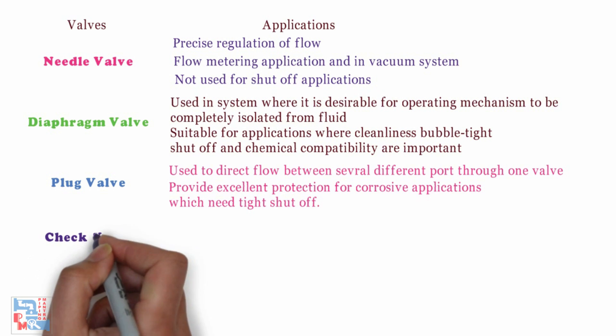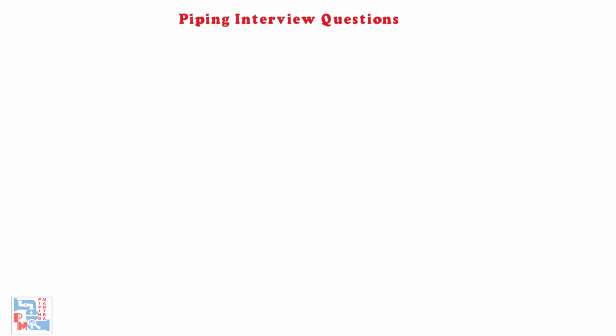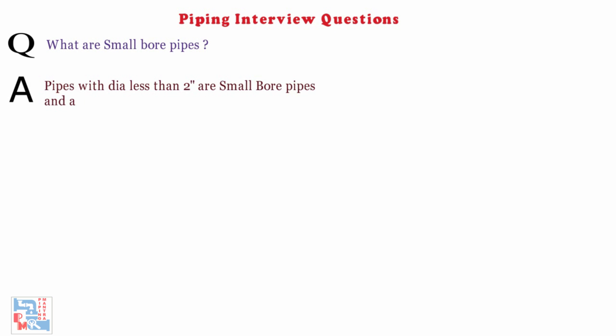Check valve. It allows fluid to flow through it only in one direction and prevents reverse flow. Next, what are small bore pipes? Pipes with diameter less than 2 inches are small bore pipes and are mostly plain end with socket weld end fittings.